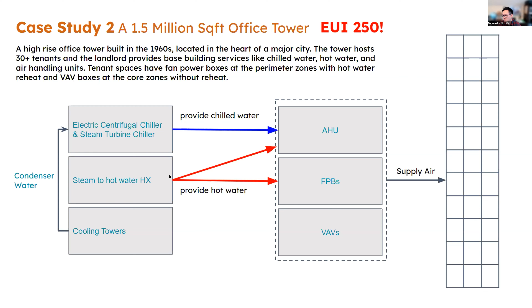And what is the problem, right? What happens when you have 30 tenants in this 1.5 million square foot building? Each tenant is going to have their own requirement for the base building service they receive. If just one single tenant says, hey, I want 42 Fahrenheit chilled water, then the building is going to supply 42 Fahrenheit chilled water all the time. There is no reset, right? Obviously, if you run your chiller that way, it's not going to be efficient, but that is a tenant requirement, and you have to do that for the entire building.